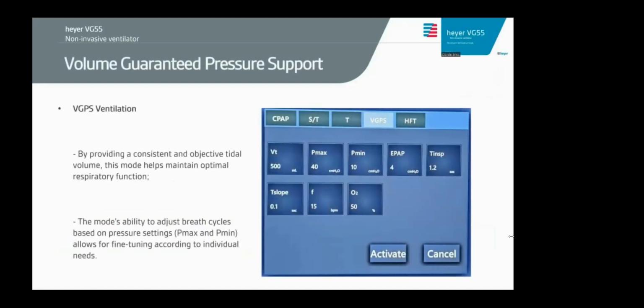In volume guaranteed pressure support ventilation mode, or VGPS mode, the ventilator ensures a specific tidal volume by adjusting pressure and following the predetermined T inspiratory setting. In this mode, the ventilator manages both mandatory breaths based on timing and assists spontaneous breaths with pressure support. When patients do not initiate breaths within the predetermined frequency interval, the ventilator takes the initiative to trigger and deliver breaths according to the preset time inspiratory value. Conversely, if the patient triggers the ventilator within the interval, the ventilator adapts to the preset trigger value, monitors expiratory efforts, and smoothly transitions to exhalation.